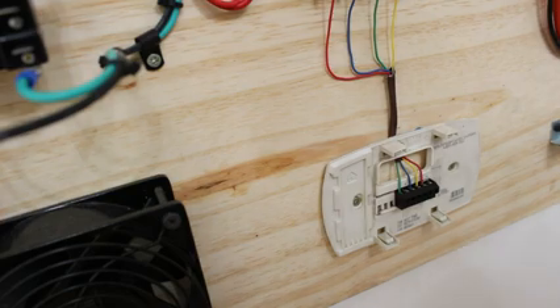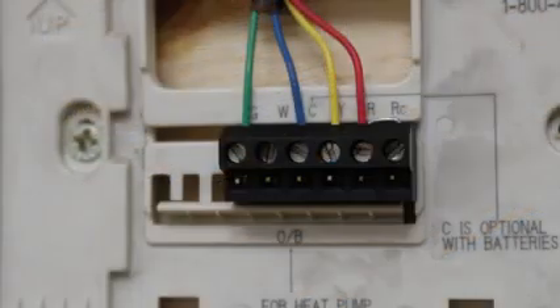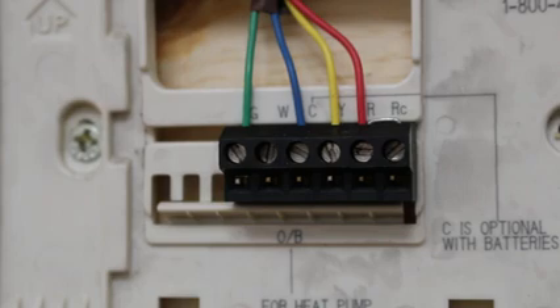We're going to pop off the faceplate for our thermostat, and we're going to go between R and C with our voltage meter. When the system has all the power on, the fastest and easiest place is definitely going to be your thermostat. You don't have to run around taking off panels, climbing into who knows where, setting up ladders, and all those things.